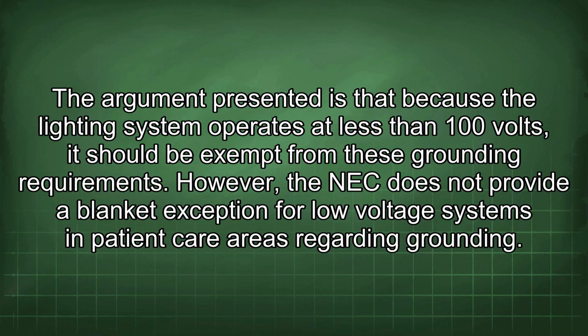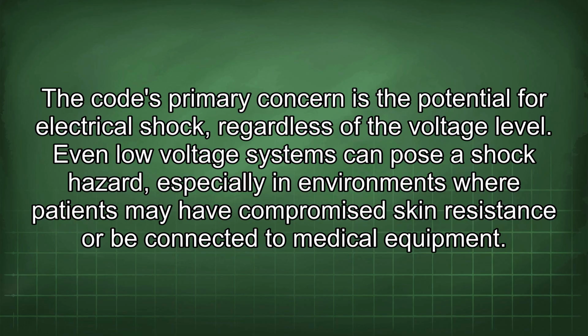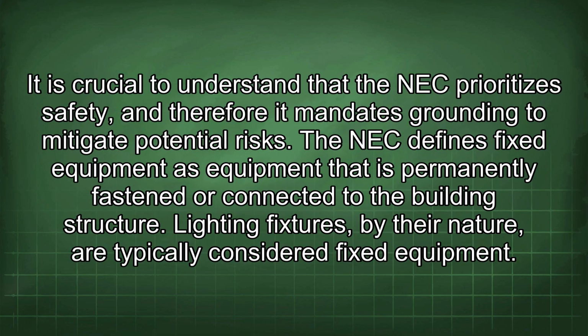from these grounding requirements. However, the NEC does not provide a blanket exception for low-voltage systems in patient care areas regarding grounding. The code's primary concern is the potential for electrical shock, regardless of the voltage level. Even low-voltage systems can pose a shock hazard, especially in environments where patients may have compromised skin resistance or be connected to medical equipment.